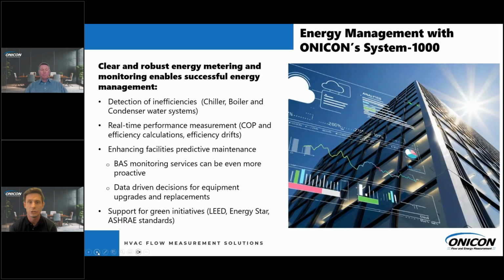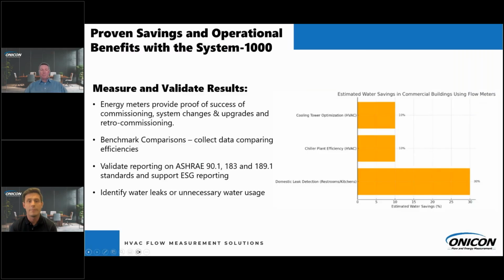There's a lot of new green initiatives nowadays. As we mentioned, there's the ASHRAE standards, there's LEED and Energy Star, and many more. On top of that, we can measure and validate results. Energy metering provides proof of success for commissioning, system changes and system upgrades, and retrofit commissioning projects. In fact, ASHRAE and the Department of Energy emphasize the importance of energy metering, especially in retrofit commissioning projects that are using measurement and verification for energy savings. And in these projects, you can save up to 20% annually on your energy bills, which is typically a two-year payback and return on investment. And a huge part of that is BTU monitoring or measuring.